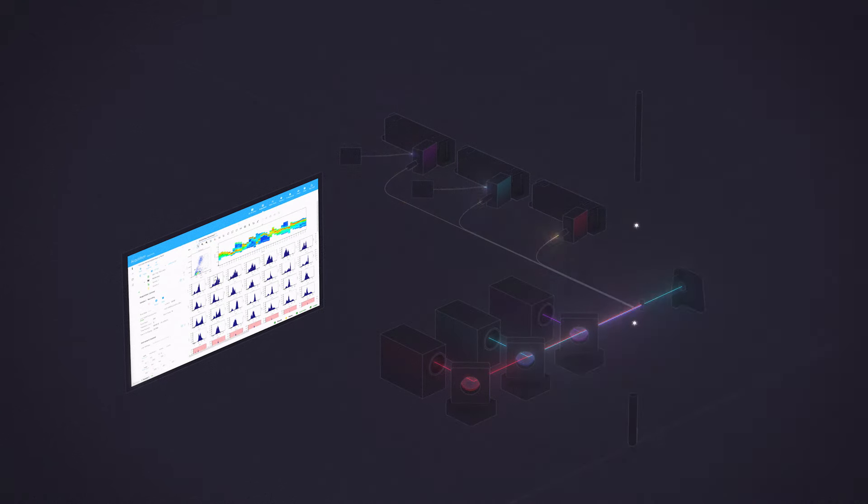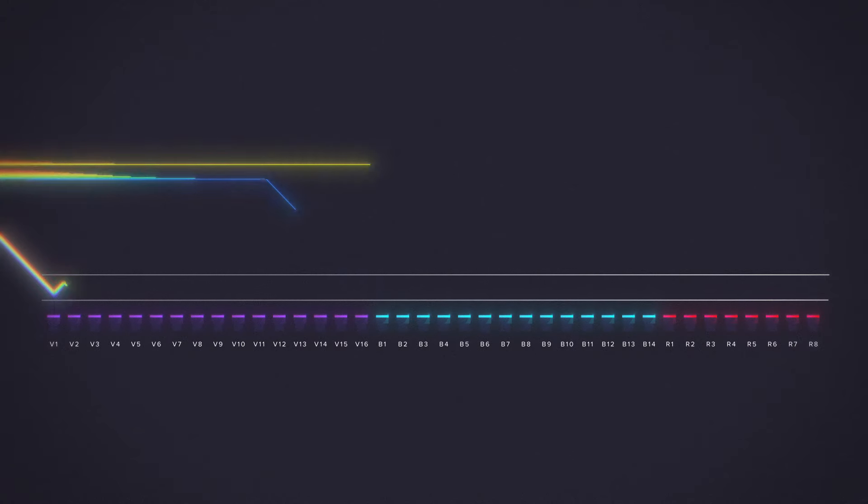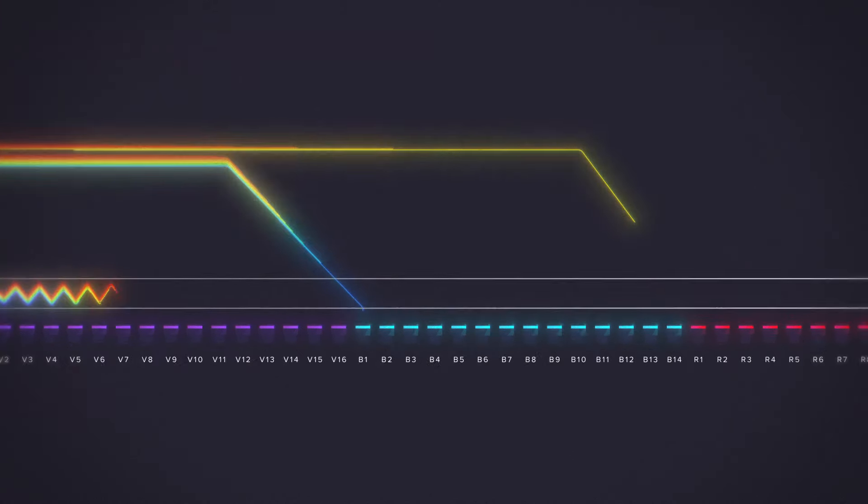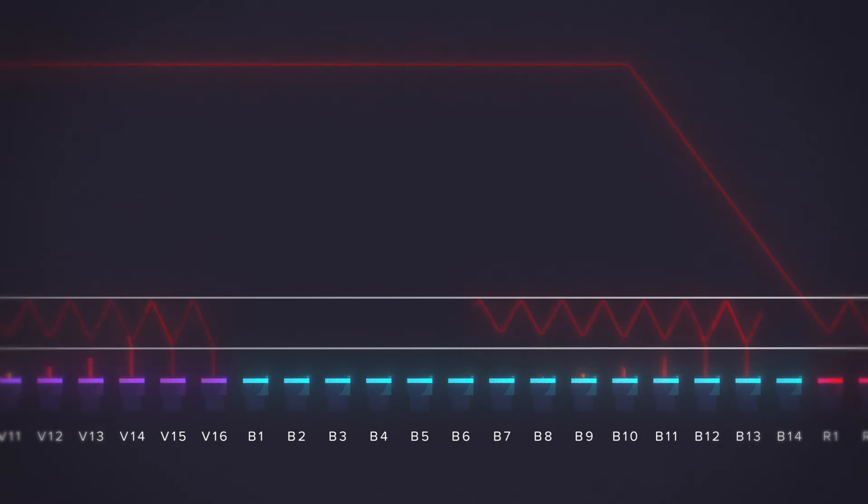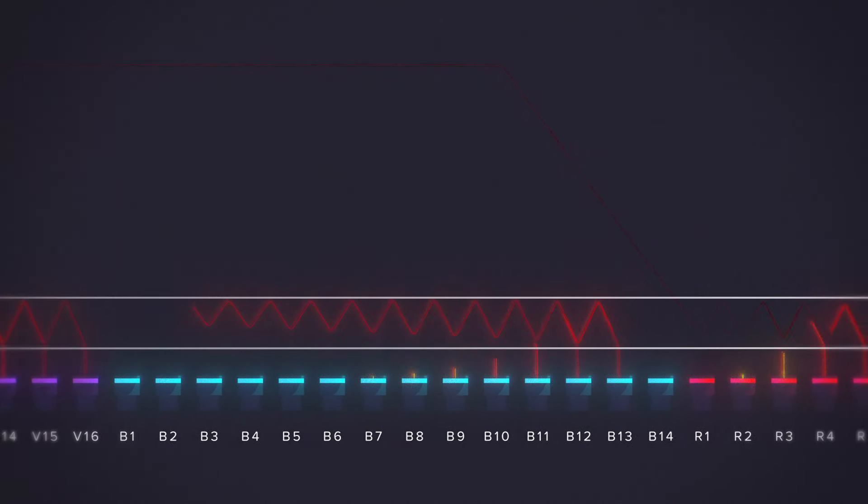Each laser has its own detector module with up to 16 APDs inside, capturing the full spectrum of light. Any fluorochrome that's excited by the lasers on the Aurora can be used without changing the filters.